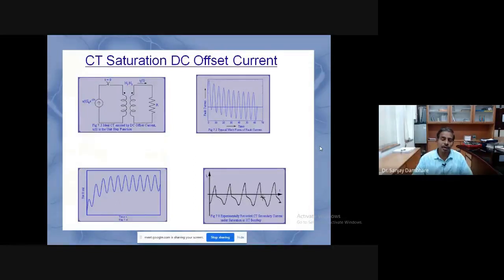And this is very difficult in a sense that these protective devices should operate during the fault condition, and during the fault condition your currents and voltages are much deviated from the nominal value. So fault current, we know, is very high, and the voltage goes to a very low value, and during that condition your relay should get the faithful replica of the current and voltages. Also, when the fault occurs, we experience DC transients in the fault current, and these high frequency transients give birth to a decaying DC current, and it causes the CT to saturate. Similarly, these transients are observed in the VT. I will come to that in the next slide.